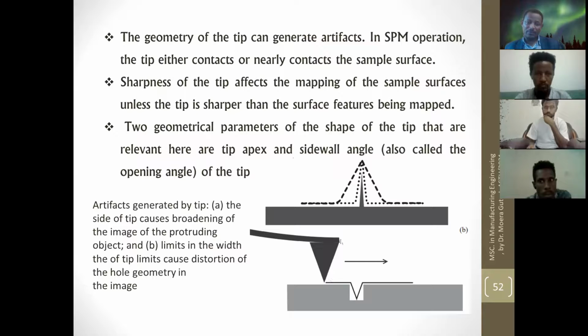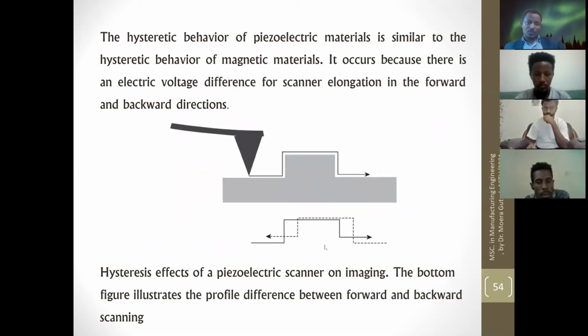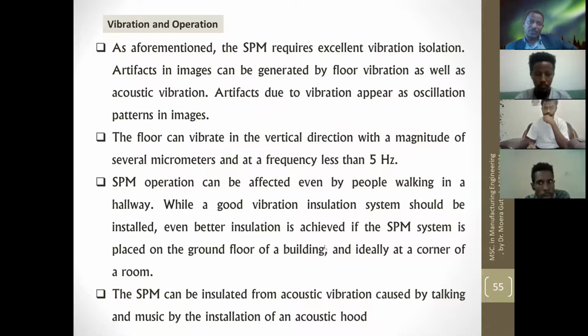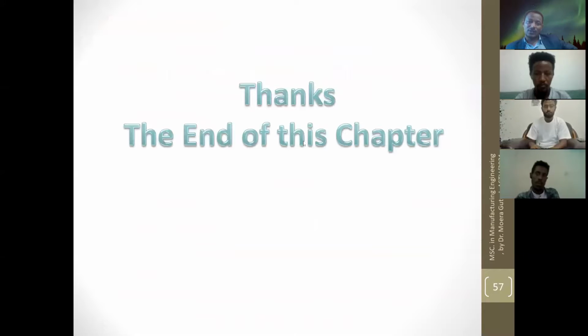The cantilever beam, either we can use a triangular one or a single cantilever beam here. You can read this one, vibration and operation. We said scanning tunneling microscopy will not work in vibration conditions. Atomic force microscopy will work with oscillation of the cantilever beam. Controlling the oscillation frequency of the cantilever is very important. This thing you have to cover yourself. So thank you very much. This is the end of this chapter.